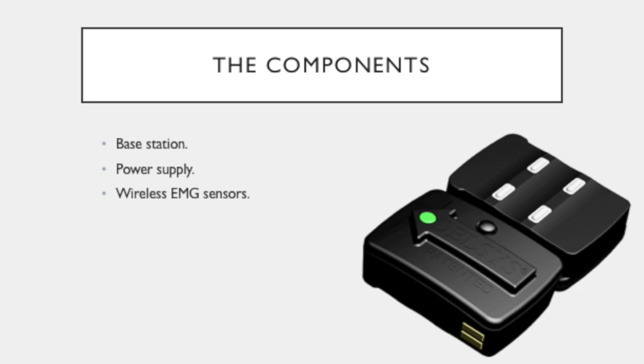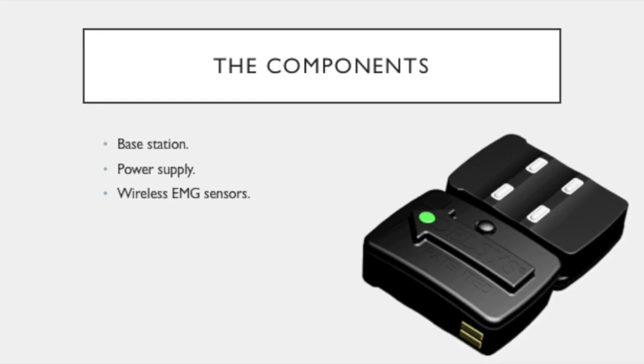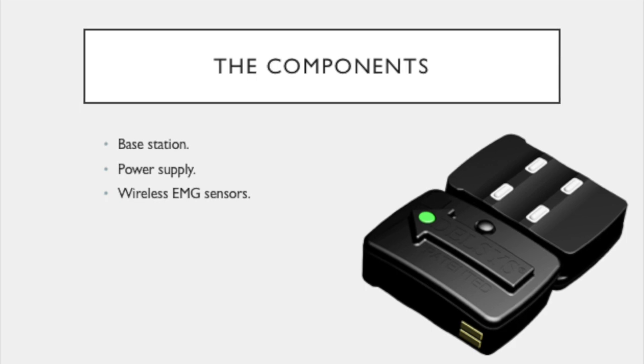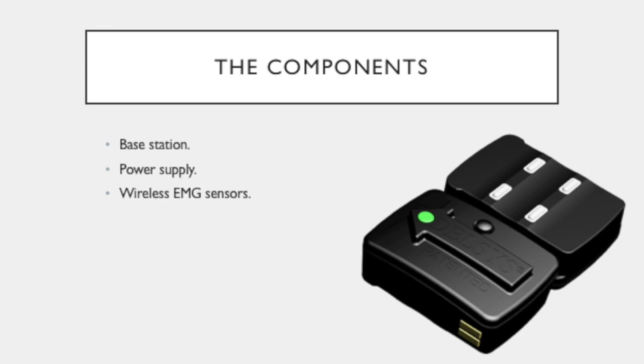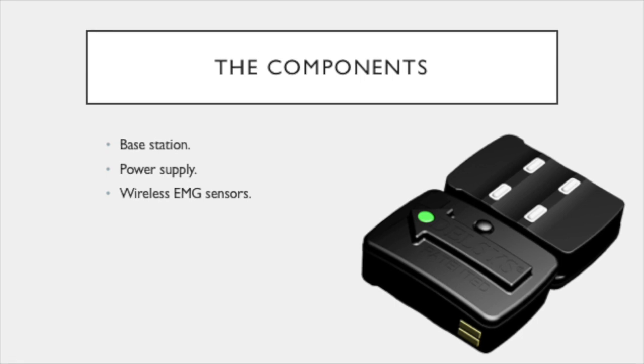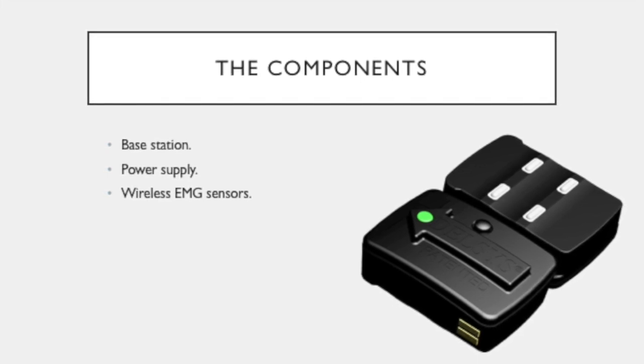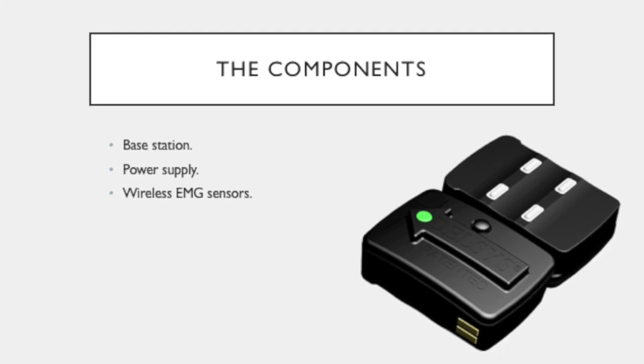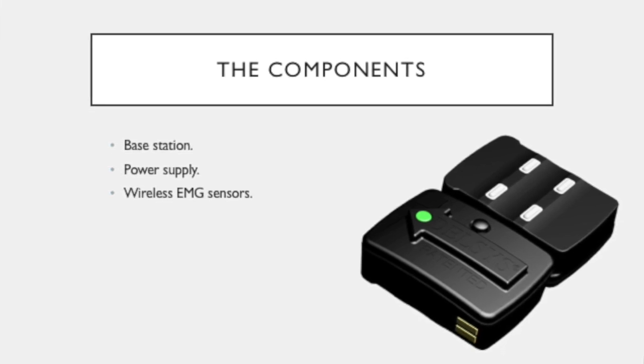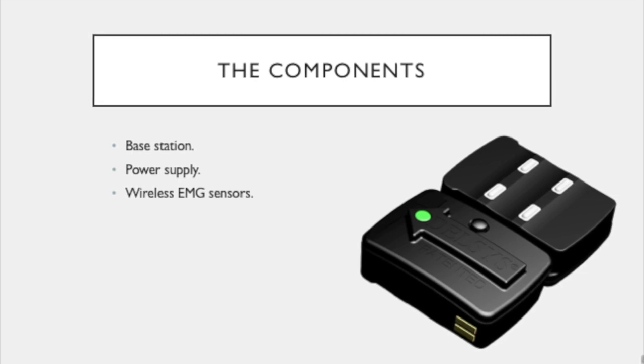The wireless EMG sensors are what set the DELSYS Trigno system apart from other EMG systems. Unlike most EMG systems, the DELSYS utilizes contact in multiple points along the muscle as this will allow the system to measure the propagation of action potentials across two points while also canceling out noise. The DELSYS system places both contacts on the same sensor unit. There are also two additional contacts which act as additional noise-canceling references.